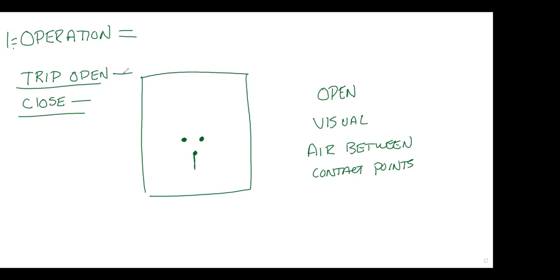Roger. So your boss man or the dispatcher calls you and says, Scott, we just had an operation on breaker B out of Singleton Ridge. What did the breaker do? It tripped open and then it reclosed. Okay. My question would be, is it closed and holding? He's going to say yes. Is it in timed operation? Yes or no, whatever that answer may be. But operation to me and in the world equates to one trip open and a close. That's one operation. Okay.